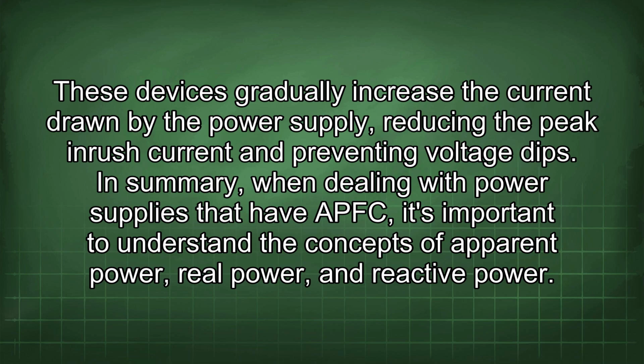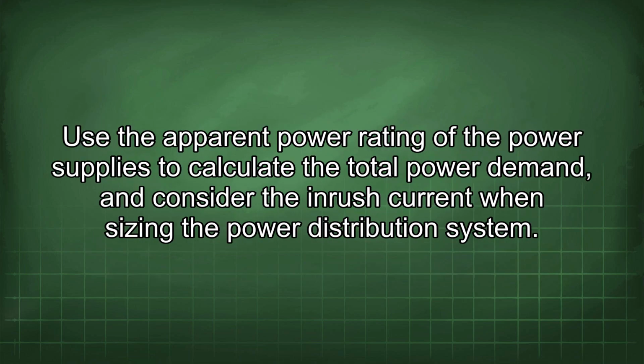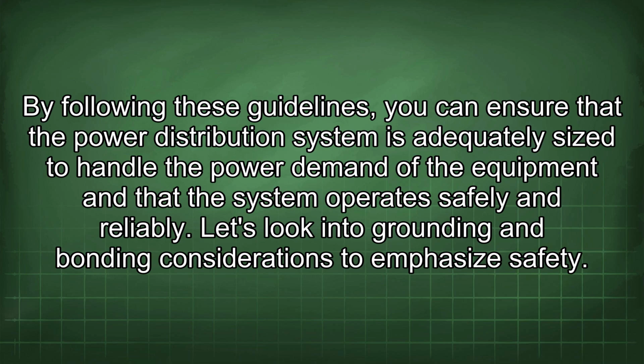In summary, when dealing with power supplies that have APFC, it's important to understand the concepts of apparent power, real power, and reactive power. Use the apparent power rating of the power supplies to calculate the total power demand and consider the inrush current when sizing the power distribution system. By following these guidelines, you can ensure that the power distribution system is adequately sized to handle the power demand of the equipment and that the system operates safely and reliably.